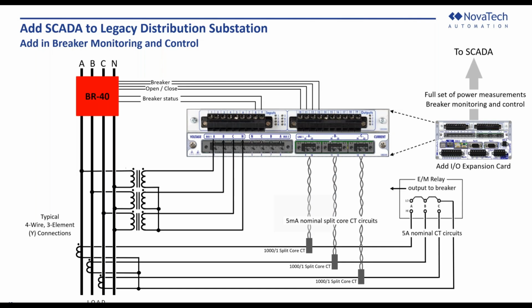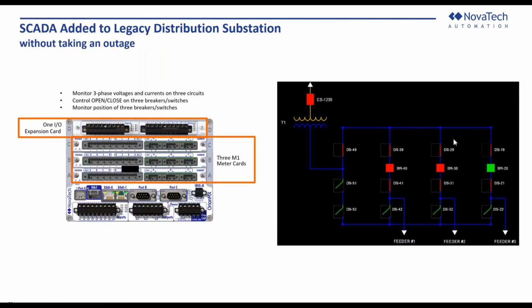So now we have automated this circuit. We provided SCADA onto this circuit, and you could do this for the other 2 circuits in the substation. And the next slide, that's pretty much what this would look like. You would only need 1 expansion card for I/O, and then you'd probably use some of the I/O that's built into the OrionMX, and 3 M1 meter cards could actually look at all of what you need on those 3 circuits, breaker 40, 30, and 20. So again, this is an easy way to add SCADA without taking an outage in a small, simple legacy substation.